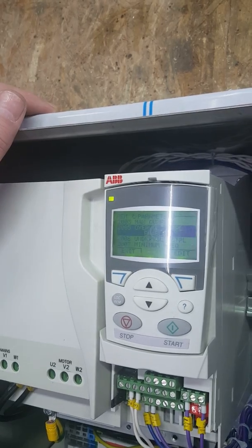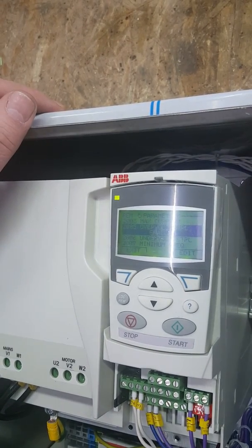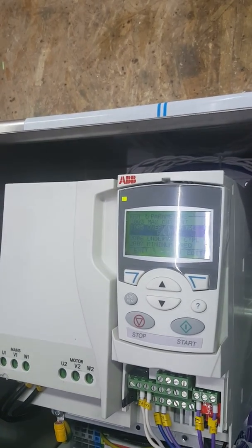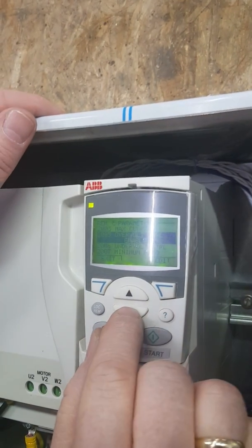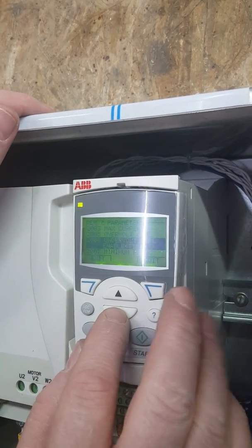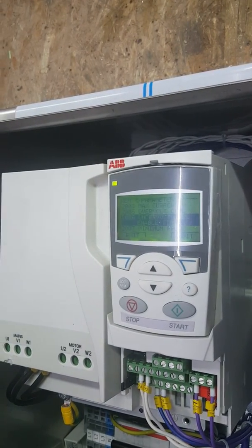Save. Then it's this overvoltage control. Enable when the power is too much, what comes back from the motor. You need the ramps, 10 seconds and 15 seconds for up. When you change the speed and you have too short a ramp, then overload comes. Undervoltage control. Enable. Also when the power goes down under 480 volts to 400 or so, then it's undervoltage. Okay.